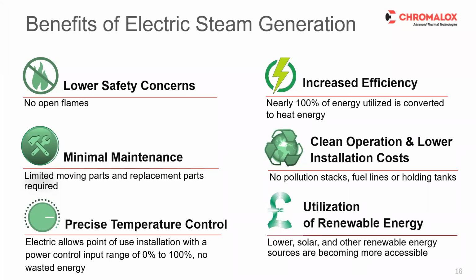So some of the benefits of using electrical steam generation is, well, first of all, there's no open flame. So that's going to have an enhanced level of safety when it comes to operating the generator, for the simple reason that we're not susceptible to getting an overpressure or a failure of the boiler pipes on an over temperature basis. If we get a fault with a traditional flame tube, that collapsing tube can result in a catastrophic failure of the boiler. And that's what a lot of the traditional blowdown controls and water level controls on a traditional boiler are there to prevent.